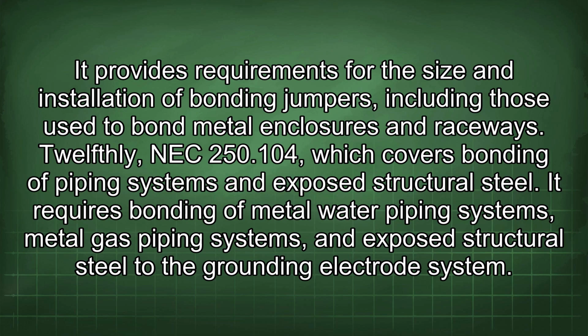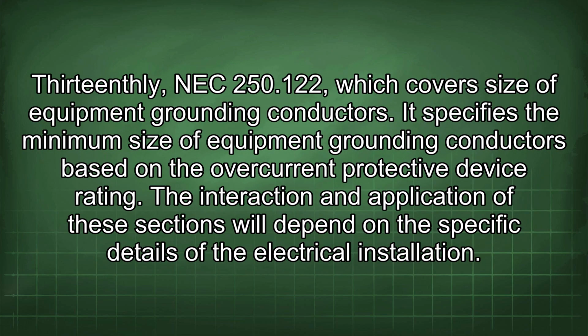12thly, NEC 250.104, which covers bonding of piping systems and exposed structural steel. It requires bonding of metal water piping systems, metal gas piping systems, and exposed structural steel to the grounding electrode system. 13thly, NEC 250.122, which covers size of equipment grounding conductors. It specifies the minimum size of equipment grounding conductors based on the overcurrent protective device rating.